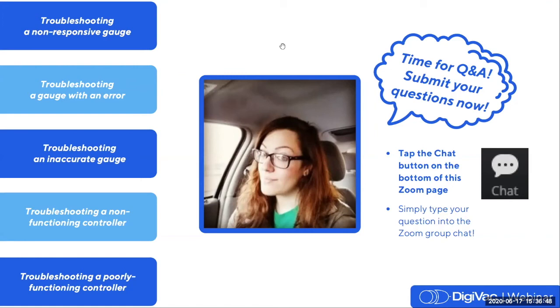The question states, when testing sensor resistance, check test lead resistance first so it can be subtracted from the measurement. 2.9 ohms may actually be 2 ohms plus 0.9 ohms test lead resistance. And this is an excellent point to make. In our facility, we use the Fluke 87V multimeter, and we've personally tested the resistance of those leads to be about 0.2 ohms.